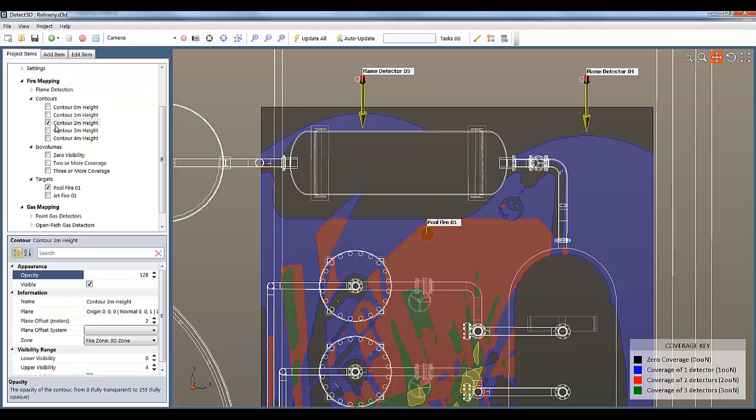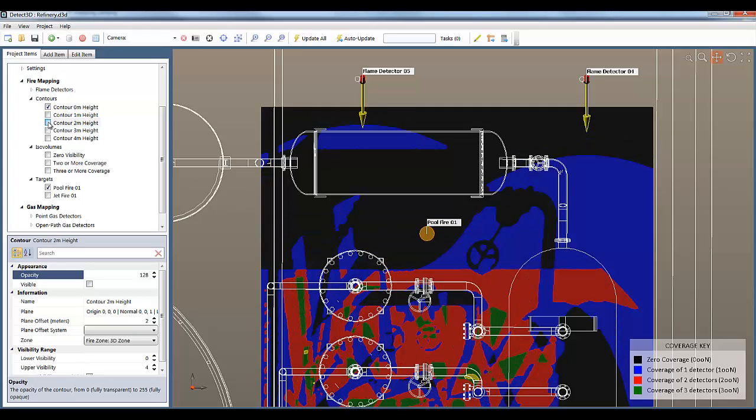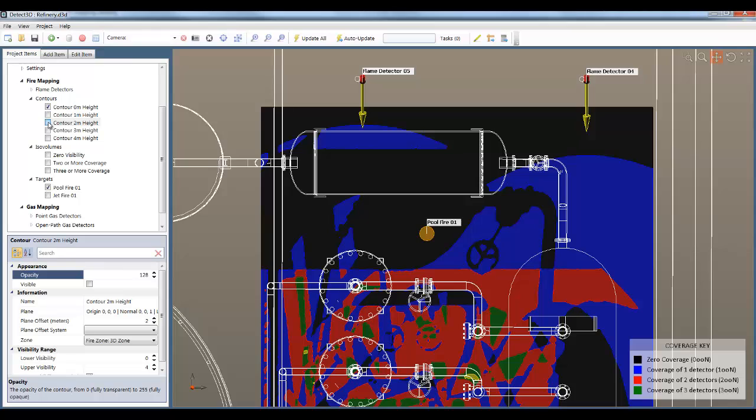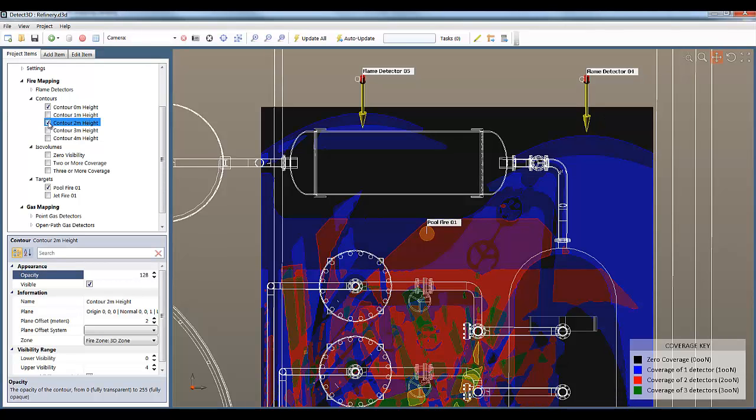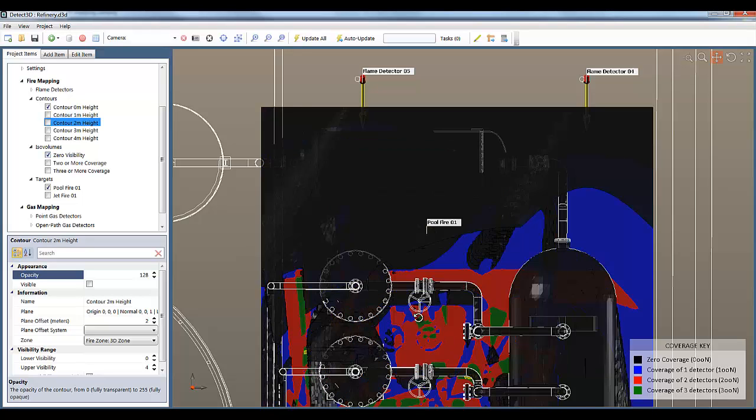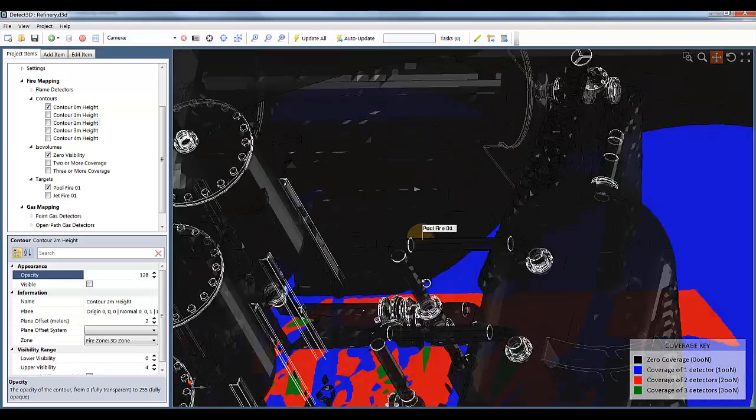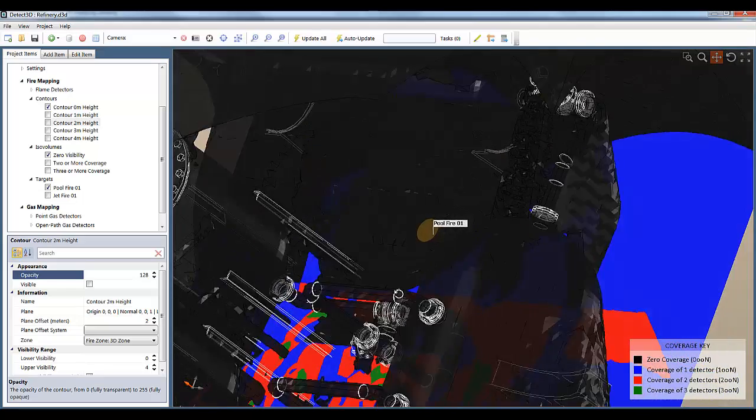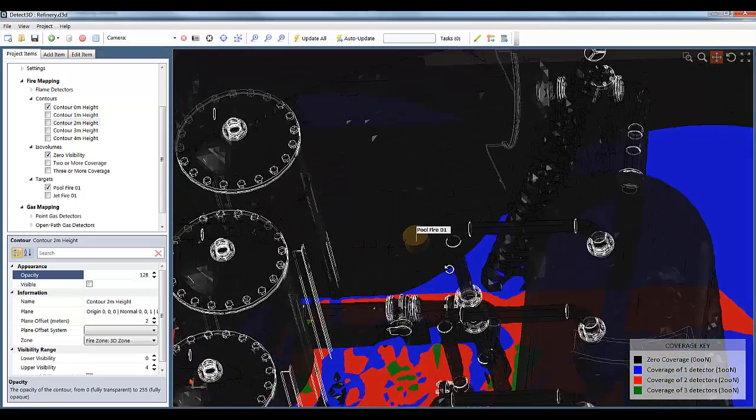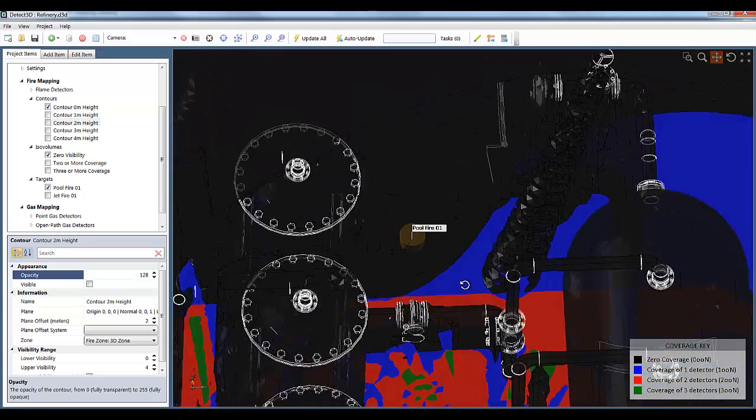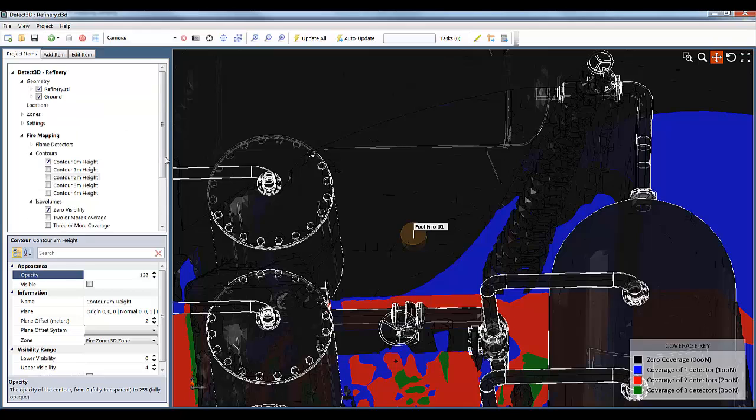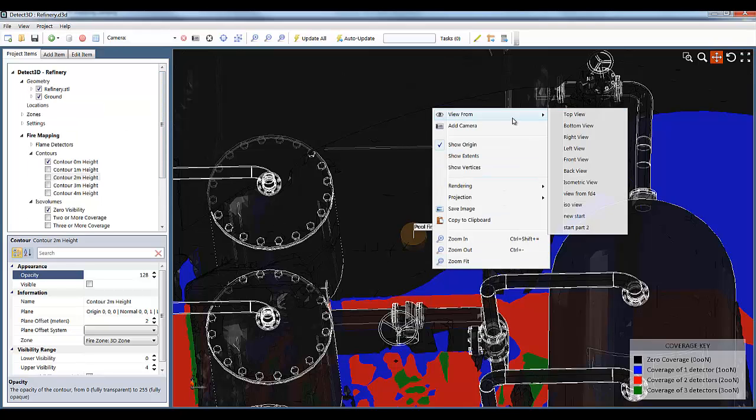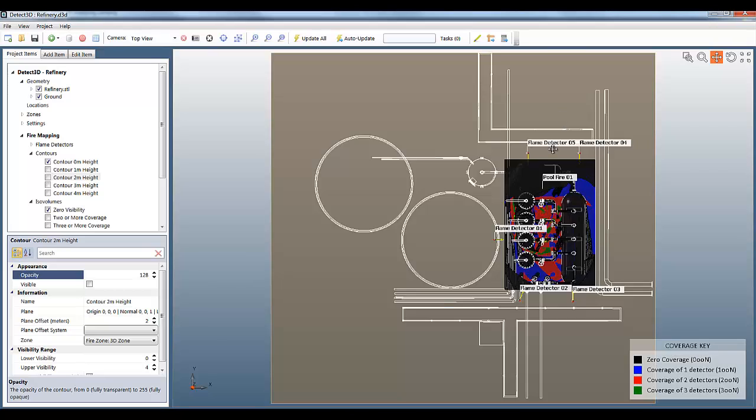However, the contour I'm showing is at 2 meters height, and if we turn on the contour at ground level we see a completely different picture. Here the pool fire is in a region of zero visibility. So which one is it? Is it visible to two detectors as we originally saw, or zero detectors? The problem is you can't really answer these basic questions with 2D mapping, and you have to look at the problem in 3D before you can see that the pool fire is definitely within a zero visibility region.